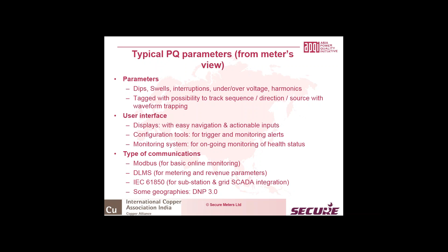Add to it the power quality meters, because they form a part of the system. More often than not, these meters do come with revenue metering functionality also. So a host of communication protocols are supported by the meters, ranging from Modbus, DLMS to the new IEC 61850, which helps the protection engineers in the utility space or the consumer space to form a network and gather the data conveniently. Some geographies do also talk about DNP3, which, if I talk about India, is not very prominent.